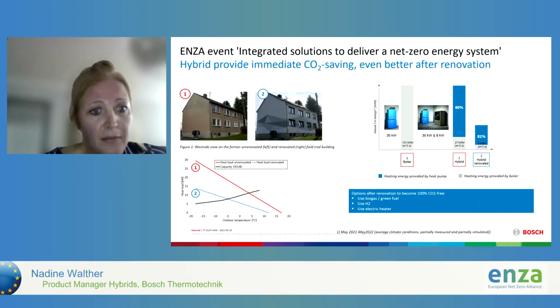And the red graph, also highlighted with the number 1, shows how the building looked in an unrenovated status. It shows the heat load is covered by a 30 kilowatt boiler on the right hand side. So beforehand, they only had the 30 kilowatt boiler in place. And afterwards, without the renovation taking place, they installed the hybrid system. They now had the 30 kilowatt boiler plus an 8 kilowatt outdoor unit. So this is a multi-family house, actually, with 6 units that are using this hybrid system. And with a hybrid system, 80% of the heating energy is being provided by the heat pump.